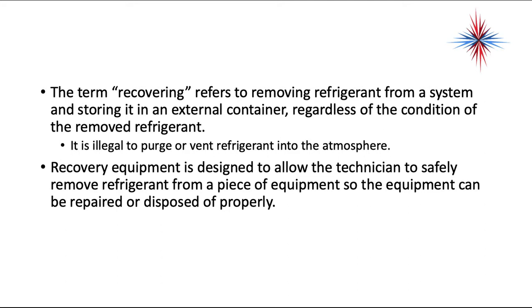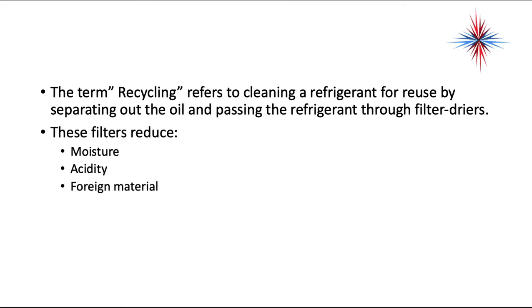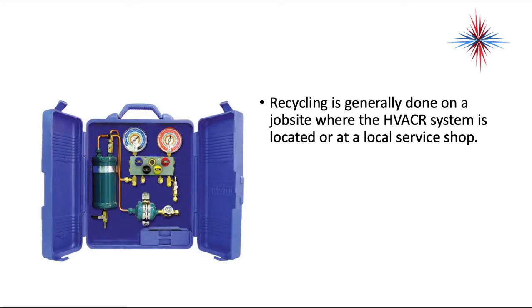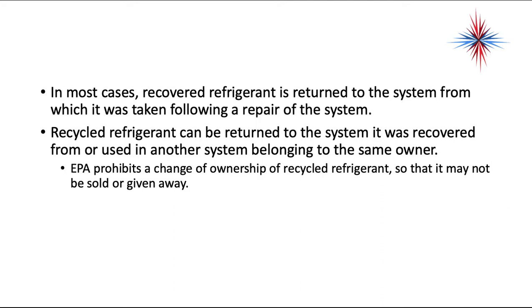Recovery equipment is designed to allow the technician to safely remove refrigerant from a piece of equipment so the equipment can be repaired or disposed of properly. The term recycling refers to cleaning a refrigerant for reuse by separating out the oil and passing the refrigerant through filter dryers. These filters reduce moisture, acidity, and foreign material. Recycling is generally done on a job site where the HVAC system is located or at a local service shop. In most cases, recovered refrigerant is returned to the system from which it was taken following the repair of a system. Recycled refrigerant can be returned to the system it was recovered from or used in another system belonging to the same owner.